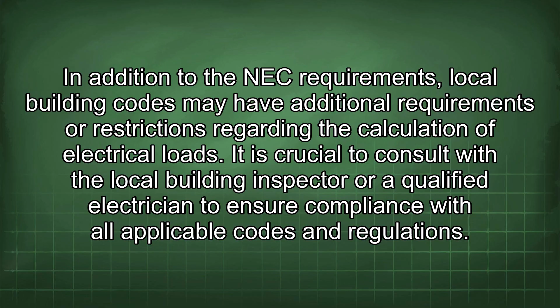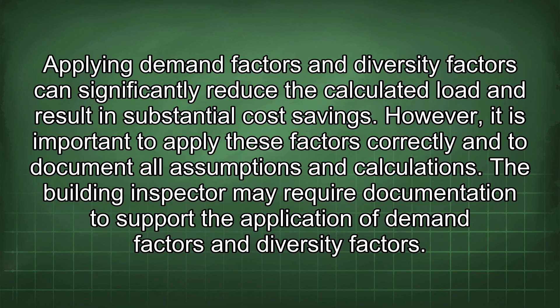applicable codes and regulations. Applying demand factors and diversity factors can significantly reduce the calculated load and result in substantial cost savings. However, it is important to apply these factors correctly and to document all assumptions and calculations. The building inspector may require documentation to support the application of demand factors and diversity factors. This documentation typically includes detailed load schedules, calculations, and supporting information.